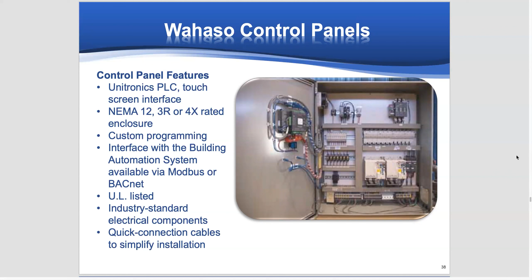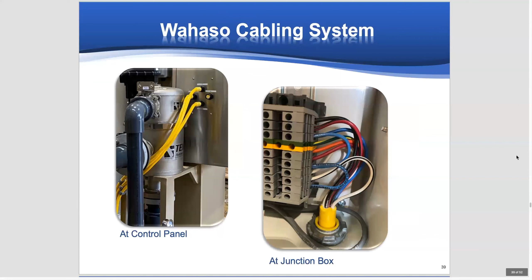Look at the picture on the right, at the junction box. When we have multiple skids, we pre-wire these systems and connect all of the devices at the junction box in this terminal strip. Then a cable comes out, and at the main control panel on the other end, there's either an 8-pin or 10-pin cable that you just click in and turn. We've made it so all 8-pin connectors are 115 volts, and all 24 volt DC signals, whether analog or pulse, are 10-pin connectors. So you can't blow something up by hooking up 115 volts to a 24 volt cable. The cables are numbered, so hopefully people will hook up the right ones to the right place.